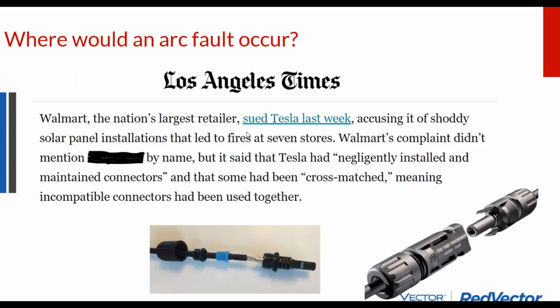So let's take a look at some arc faulting. Arc faulting can occur within the circuit itself without any pathway to ground. And so if a connector is loose and it's not making a tight connection, you can get an arc fault. If you over crimp or under crimp a connector, if you over crimp and then you bust some threadings off of the copper wire, and then now you have little copper ends that are cut, and there's a little gap of air between that and the metal connector, which should be a more solid contact, but it's not. You can get a little arc current between that.